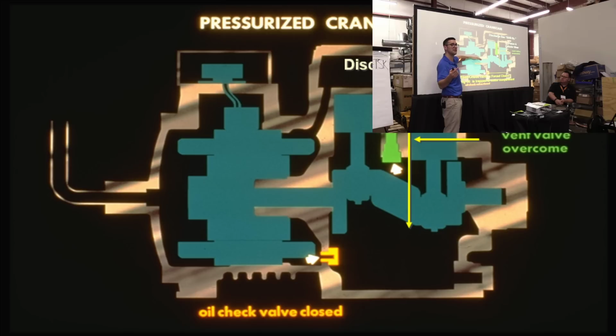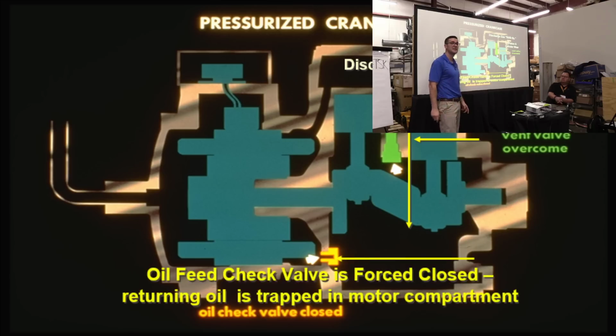My Sentronic trips off. So you as a mechanic get called at 3 o'clock in the morning, you come in and you look at the sight glass, and what does the sight glass look like? It's oil, it's good. Oh, just a Sentronic, it's a nuisance trip. Oh, it starts up. Three days later, one of your buddies goes back to work on the thing. It was off on Sentronic again. I looked inside, it was good. I reset it again. What's the issue? Blow-by.